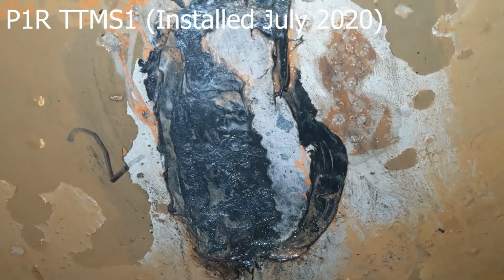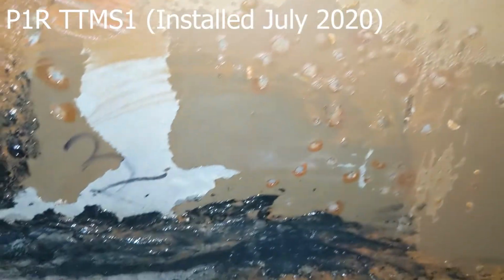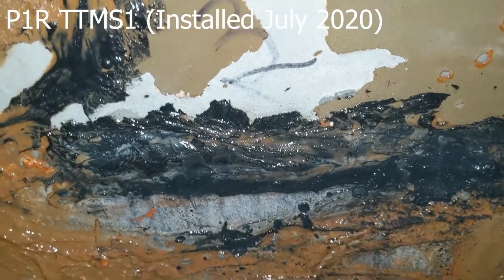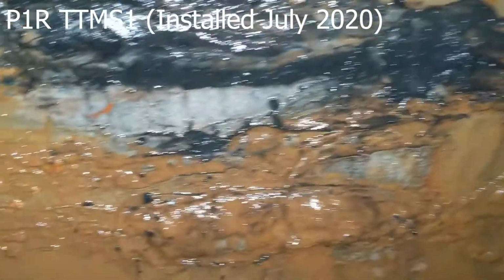It's sensor number 2. Okay, we wiped all of these down just to wipe off the red silt that had formed on them. Here's sensor number 3, and we can see evidence of bubbling. Just go at it from this angle to see a little bit better. The bubbling underneath the polysulfide in particular.